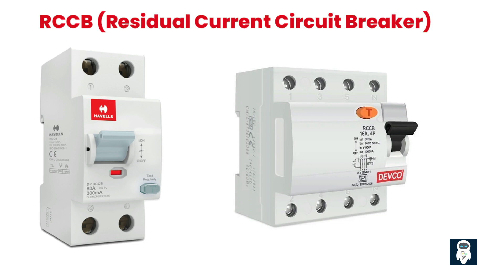When the RCCB detects a significant residual current, typically above a predetermined threshold, such as 30 milliamps, it quickly trips or disconnects the circuit, cutting off the power supply. This rapid disconnection helps prevent electric shock and reduces the risk of fire caused by electrical faults.